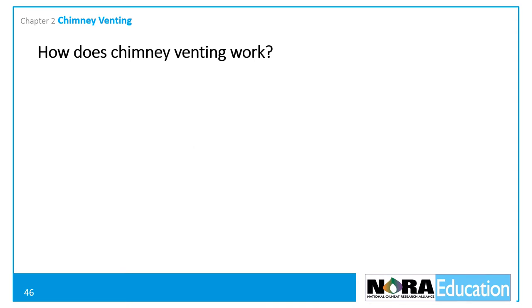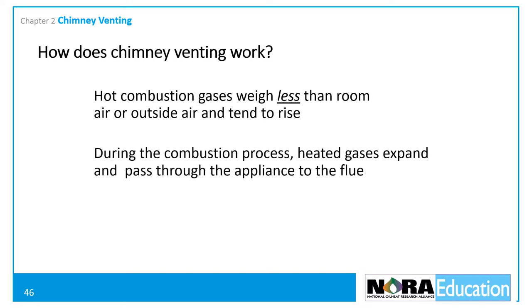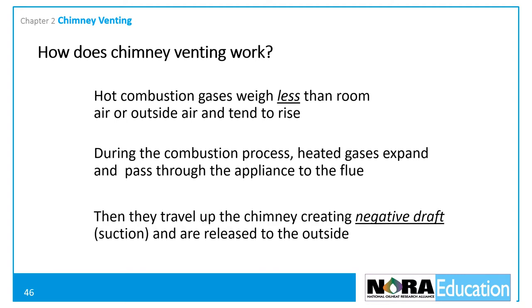Here's how chimney venting works. Since hot combustion gases weigh less than room air or outdoor air, they tend to rise. During the combustion process, heated gases expand and rise through the heating appliance to the flue pipe. They then travel up the chimney, creating negative pressure or suction, also known as negative draft, before being released to the outside atmosphere.